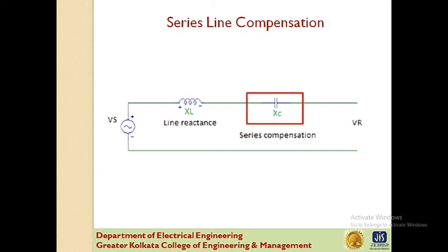Now, series compensation addresses a fundamental aspect of voltage stability, namely the electrical distance between generation and load center. In this respect, it is a very efficient countermeasure to instability. It effectively reduces the line reactance and improves the steady state stability limit. Because of the series capacitor, capacitive reactive power is directly injected into the line and voltage stability is also improved.